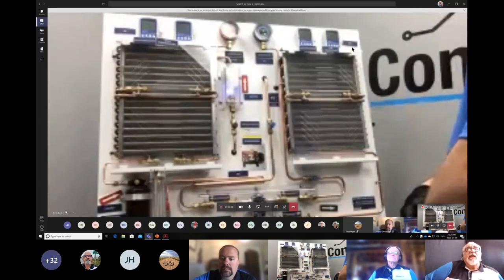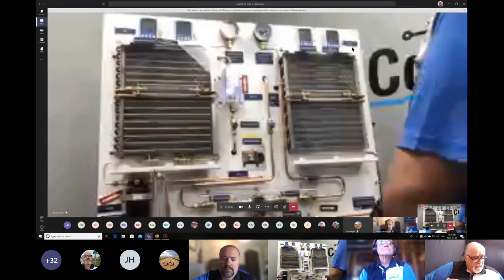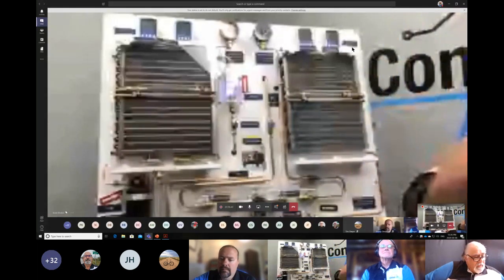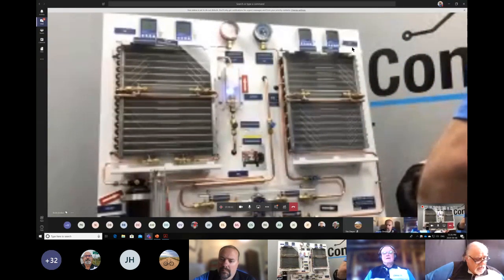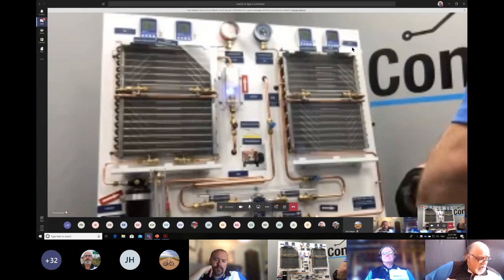Let's give it one more second and give me the numbers one more time. Okay, I'm at 32 PSI and 39 degrees. So 32 PSI is right around 33 degrees.